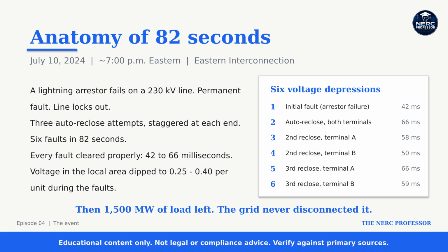In the area around the fault, voltage sagged to between 0.25 and 0.40 per unit. Now, here's the question that matters. Routine fault, normal clearing, standard reclosing practice. Operators see this every storm season. So why did 1500 megawatts of load walk off the system? Hold that thought. The answer is sitting inside the data centers.